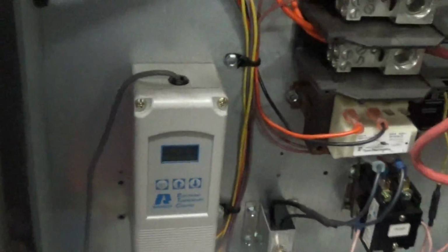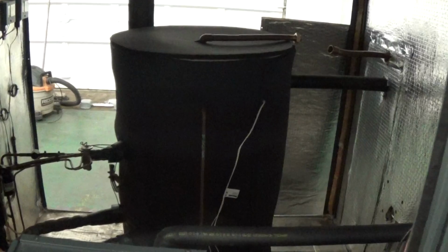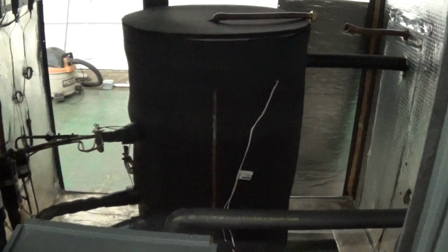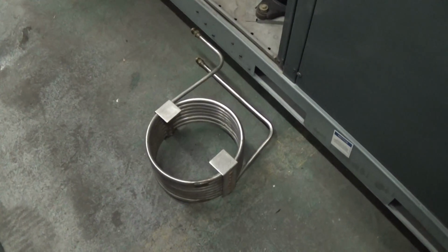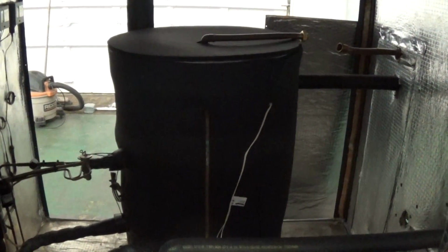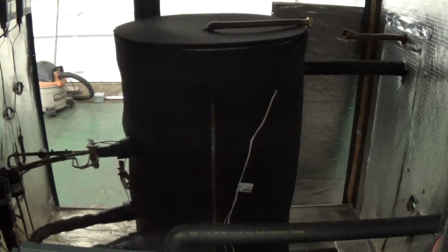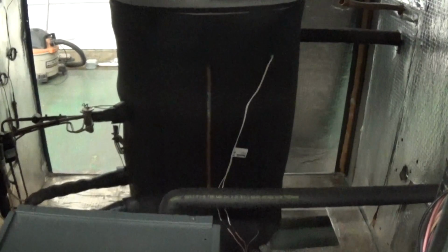So we've got both compressors running now. We're starting to chill. We're down to about 67 in this case. Now we have an insulated tank. Let's check one thing here. This unit has a 55-gallon insulated tank. There are 2 circuits. Not only are there 2 compressors, there are 2 refrigerant circuits and 2 heat exchangers. This is a very small example off a little 1-ton chiller of a coil-type heat exchanger. There are 2 of them in this tank. One's actually a little bit taller and fits in the other. They both have effectively the same amount of surface area for the same amount of heat transfer.